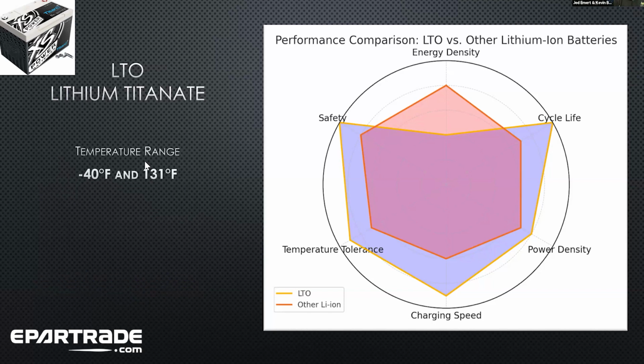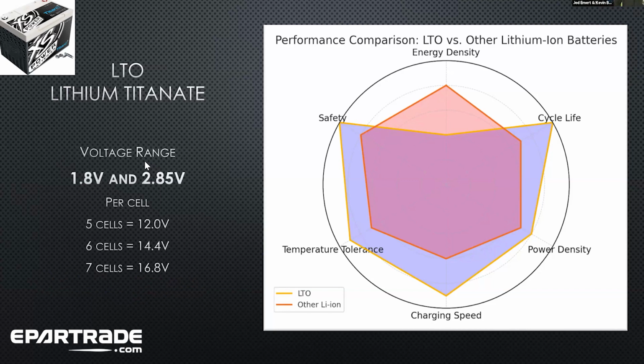Now, LTO can operate at -40 Fahrenheit up to 131 degrees, so you can see that wide temperature range. Remember, lead acid was -4, we're looking at -40. So that's a great cold weather product. The voltage range, 1.8 to 2.85. So now 12-volt batteries end up being 5 cells, 6-cell batteries end up being 14.4, 7 cells 16.8, etc.